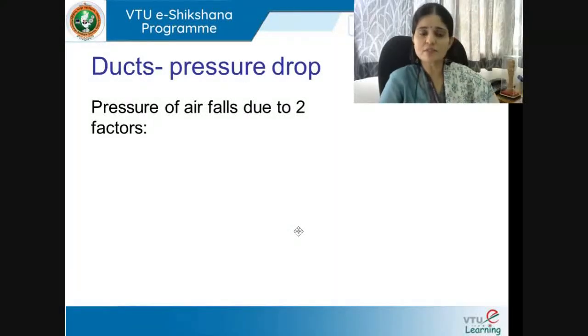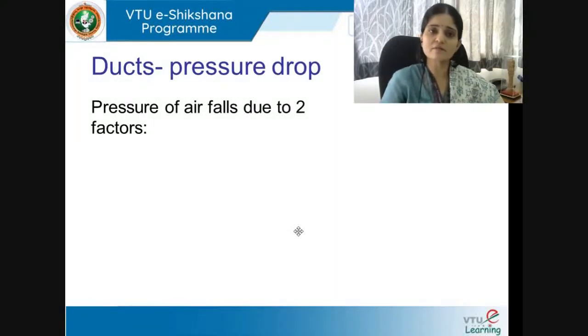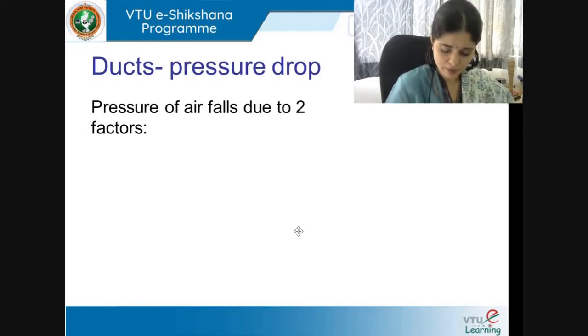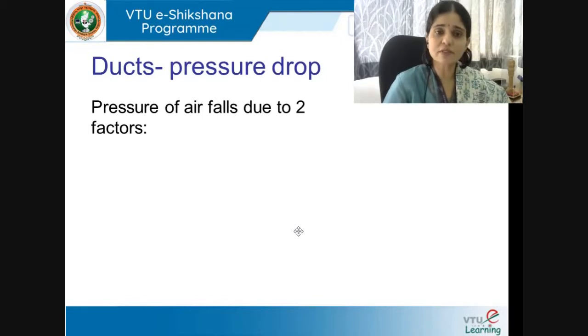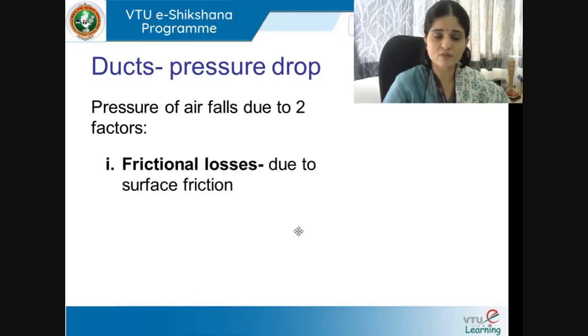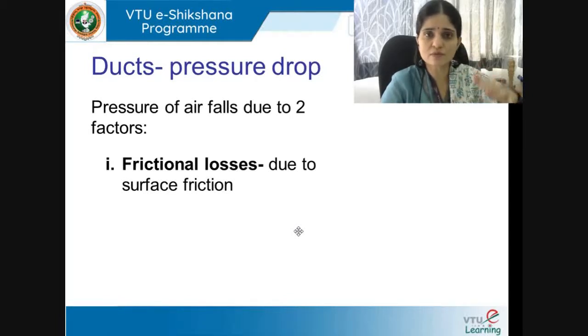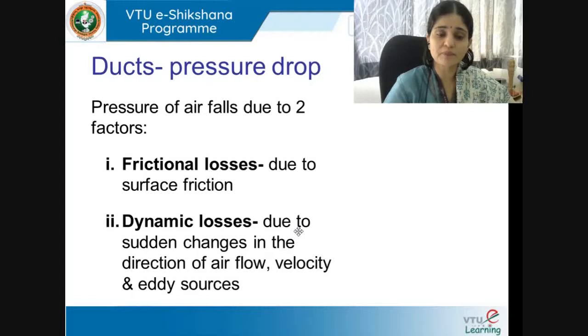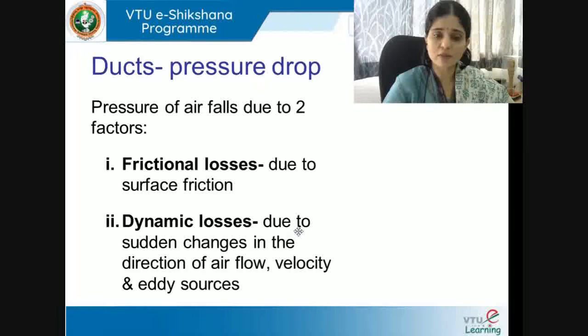Pressure drop is a serious concern in duct design. The pressure of air falls due to two factors: frictional loss — because something moving on a surface encounters friction — and dynamic loss, which is due to sudden changes in the direction of airflow, velocity, and eddy sources.